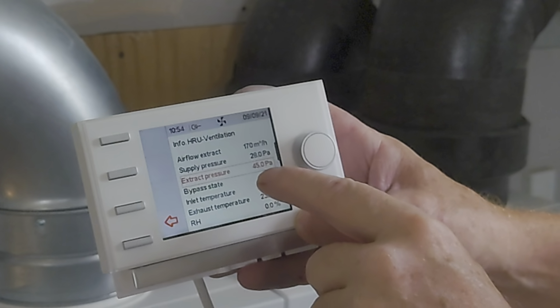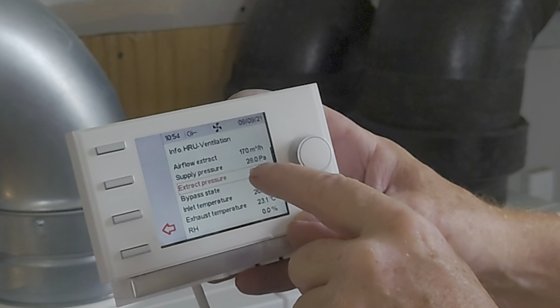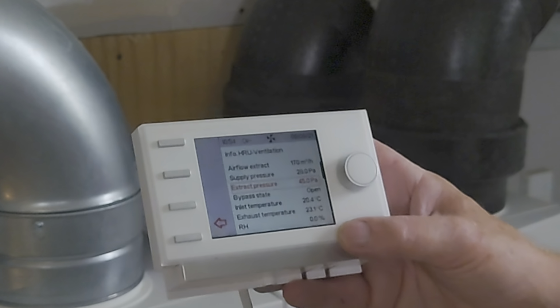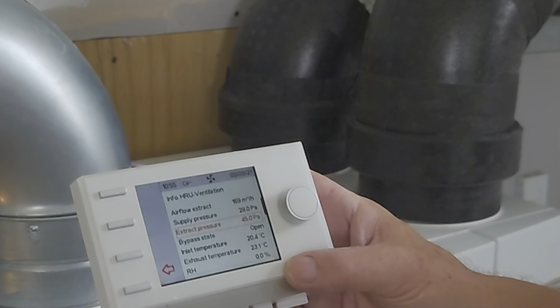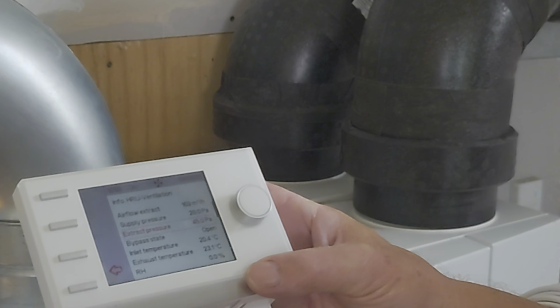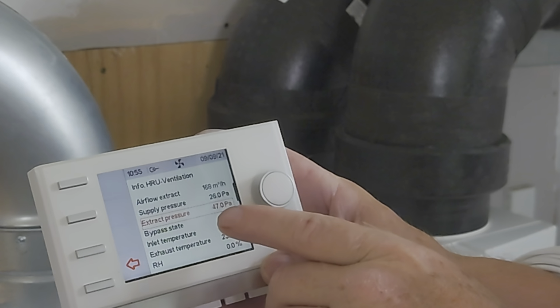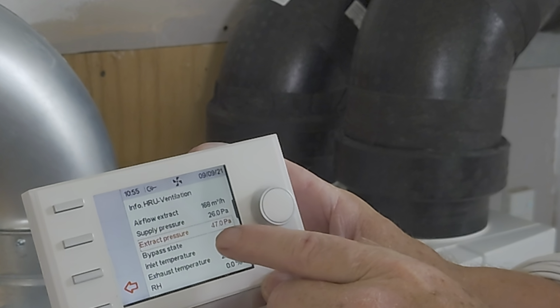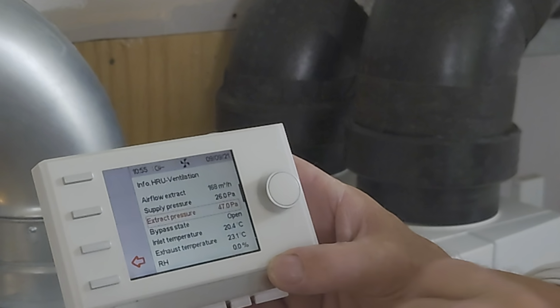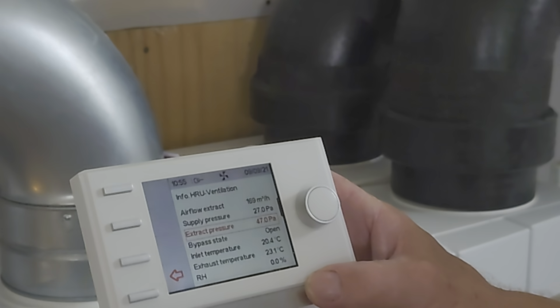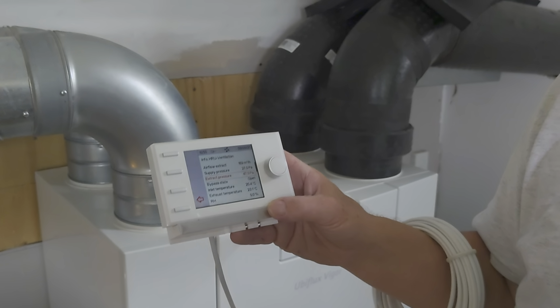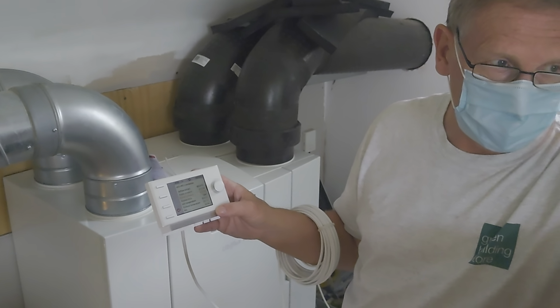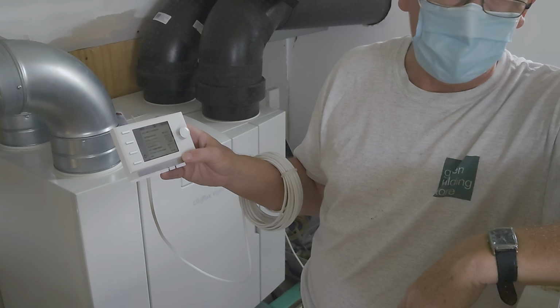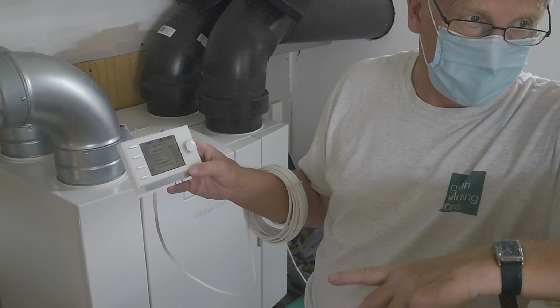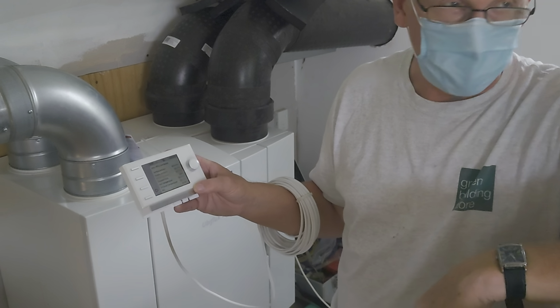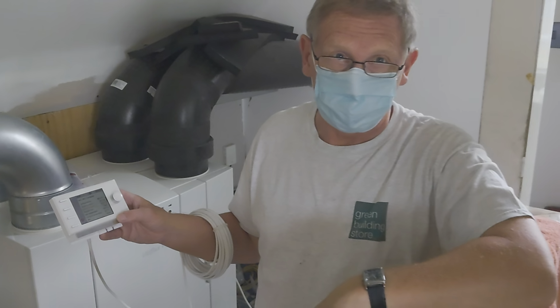On to air pressures - your supply system pressure is 28 Pascal, which is very low, so that means the fan isn't having to work hard at all. The extract is a little higher at 47, probably just fluctuating a bit. Again, that's very low - we're usually trying to design somewhere between 40 and 60 Pascals. The extract pressure is probably a little higher because it's having to suck through that filter.